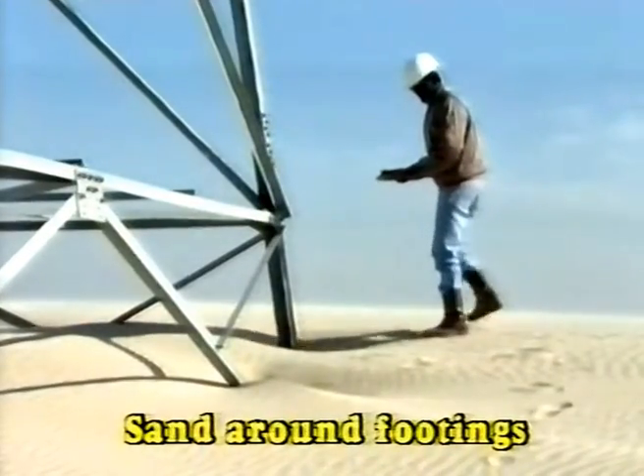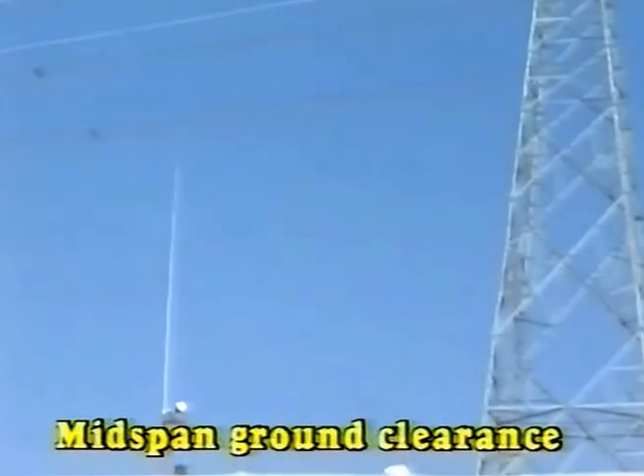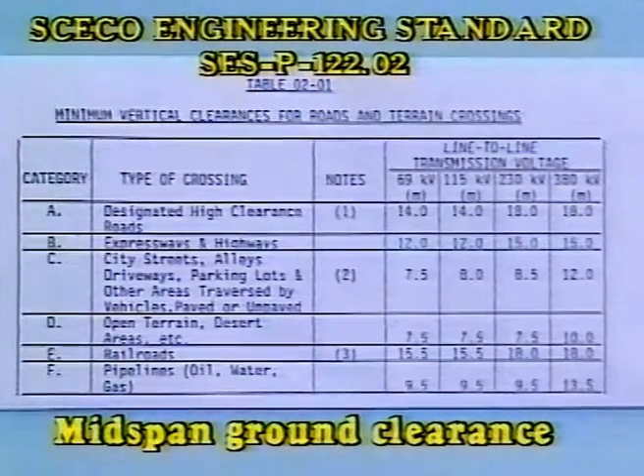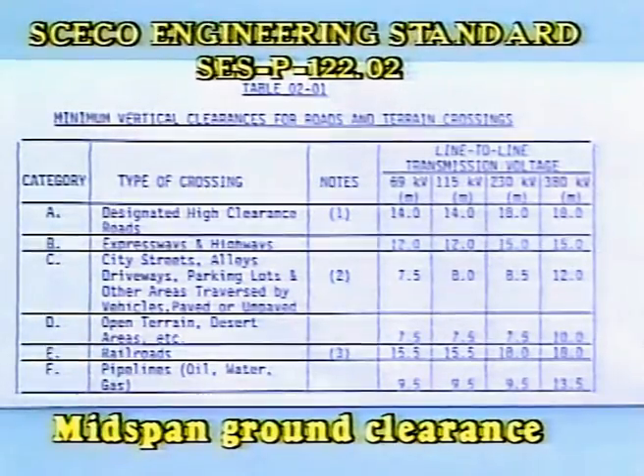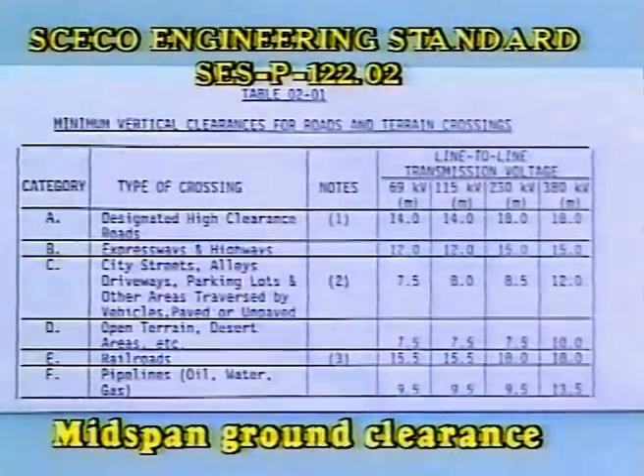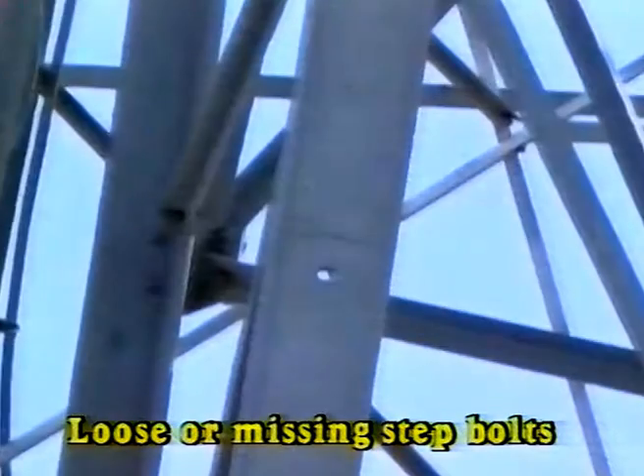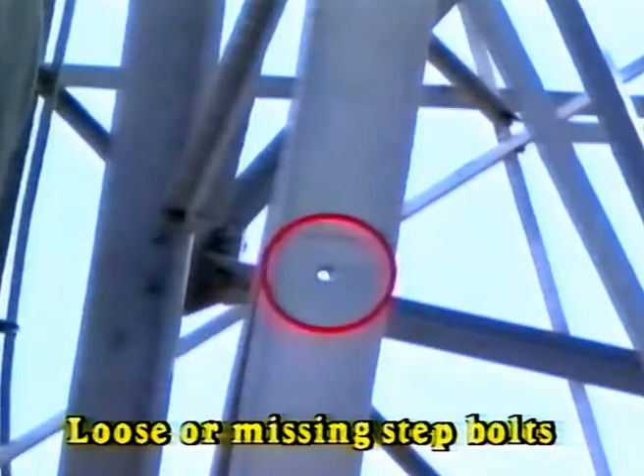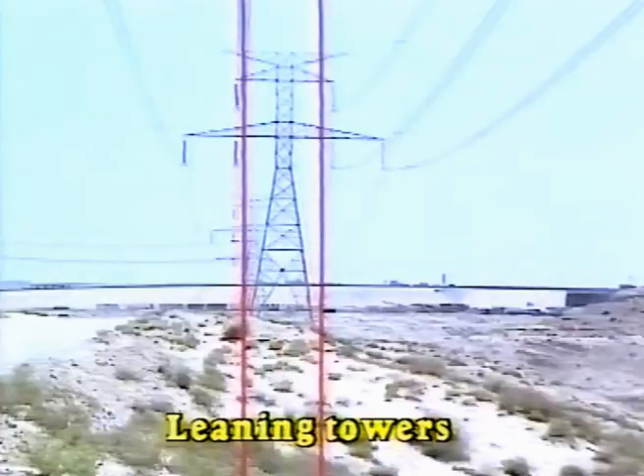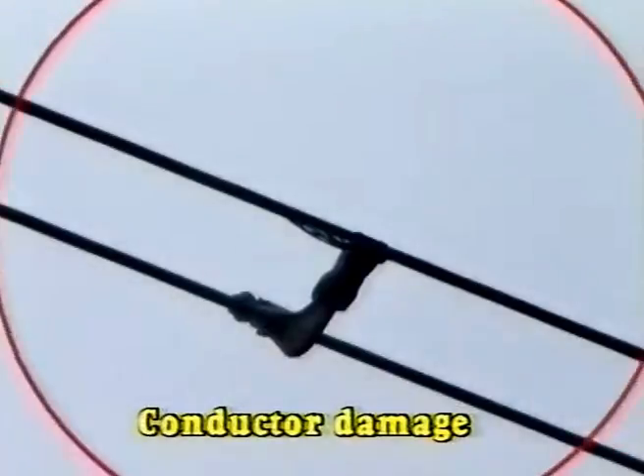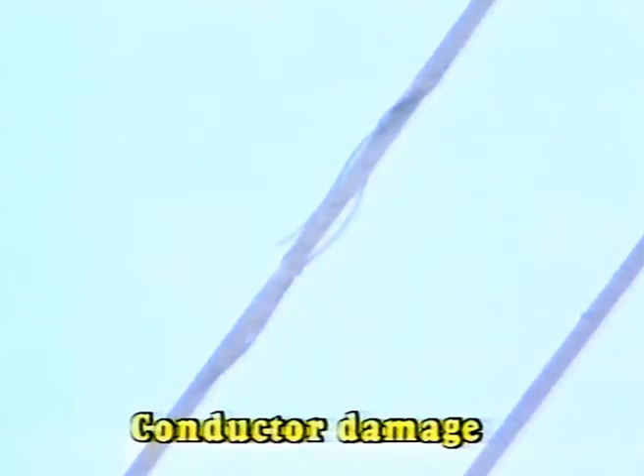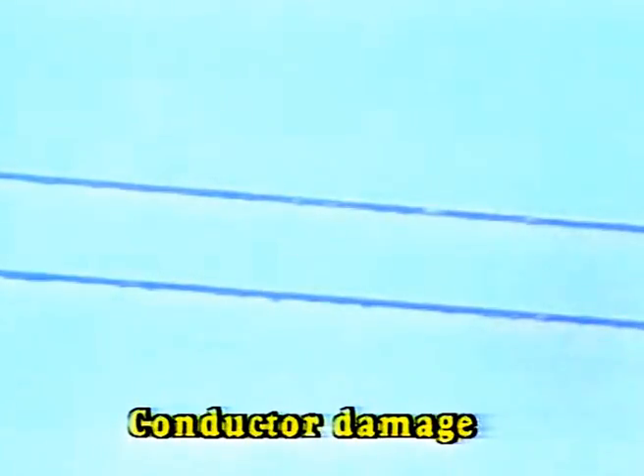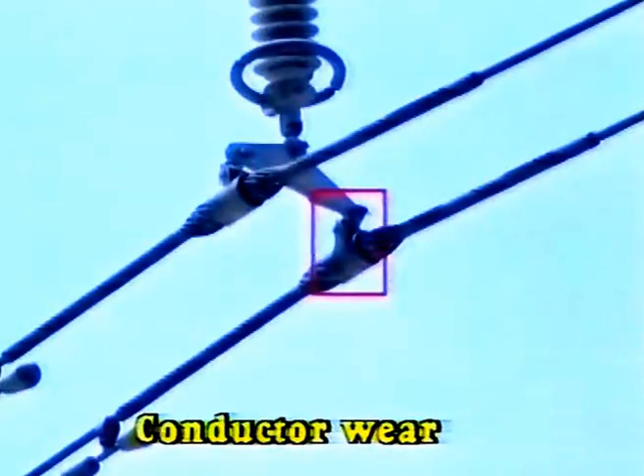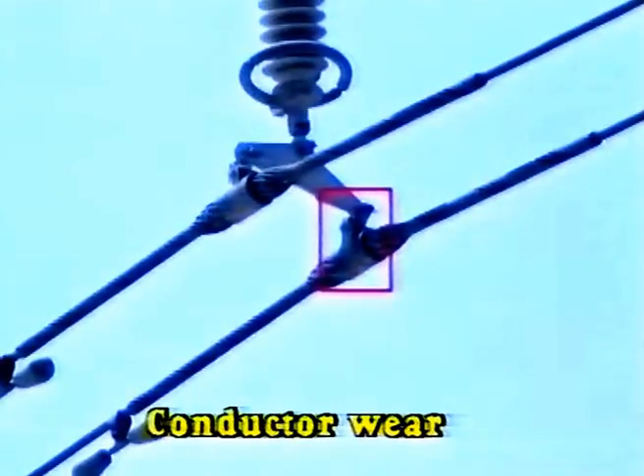Sand around footings. Mid-span ground clearance. Minimum ground clearance should be in accordance with this table. Loose or missing step bolts. Leaning towers. Conductor damage. These may be broken strands, corrosion, or burn marks. Conductor wear around connector and armor rod.